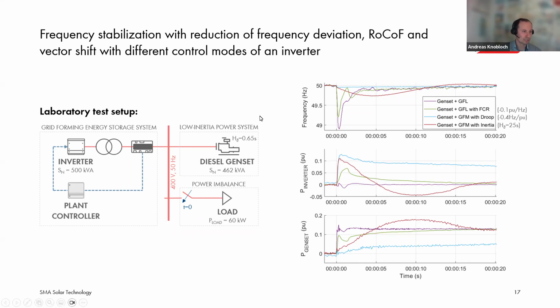And here you see the laboratory setup on the left side. It consists of a diesel generator of 462 kVA that has a very low inertia constant H of 0.65 seconds. It also incorporates all the necessary mechanisms needed for inertia provision, for frequency containment, and for frequency restoration, so primary and secondary reserves. This way it represents a low inertia power system in our case. And we now apply a power imbalance to this system with a load of 60 kilowatts, approximately 13% of the diesel generator's power.